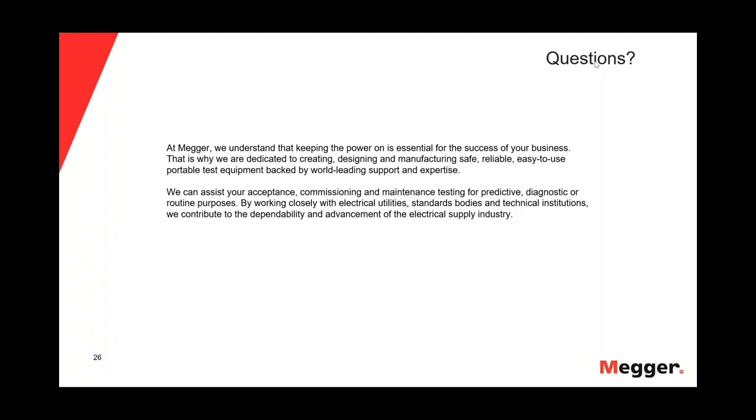For the VLF test, it's very often that sometimes we have a fault during the VLF test. And there is a paper or an article of Dortmund Wasser und Energie, that is a German company, in which they established that for the VLF test, during the first half hour, we have almost 75% of the faults, okay? But for the tan delta test, I will say that it's very untypical to have faults. But maybe just as a brief comment on this, there is not a direct relationship between tan delta value and breakdown. You cannot say if I have a tan delta of X, that means I will have a breakdown of Y, okay? There's no direct relationship.